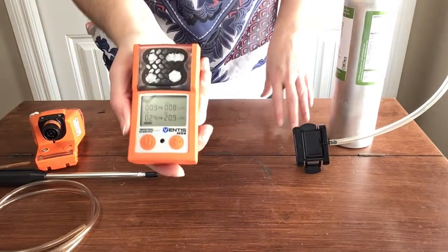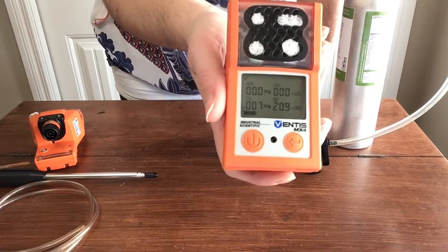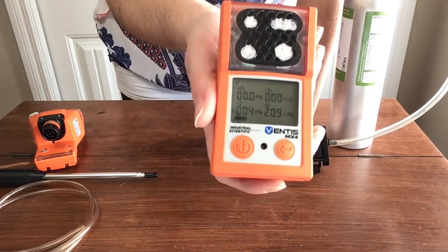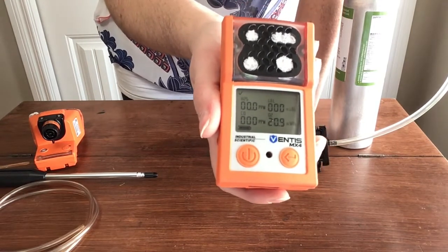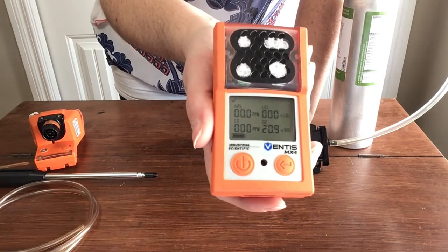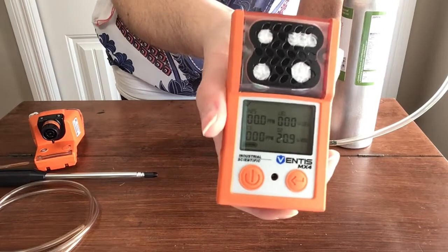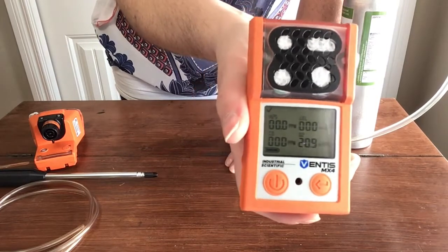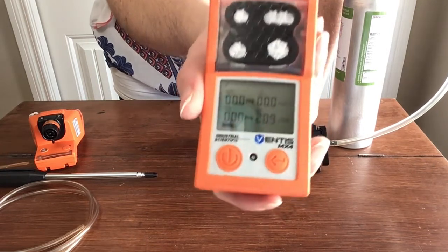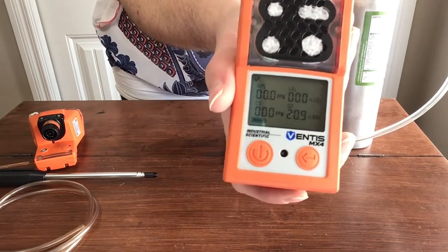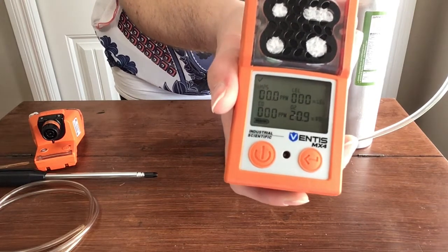Okay. So now once I've done that, you're going to see that it's going to go back to the normal operation screen, and now you're actually seeing numbers instead of those B's that you were seeing before. Okay, so this is what it's actually reading right now. You just saw a few numbers in, maybe it was the CO, and that was just the gas dispersing from the sensors, okay, the leftover gas from our calibration. So give it a moment. We've got our oxygen at 20.9, which is normal, and then we've got no H2S here, and we've got no LEL, and we've got no CO, which is what we want.